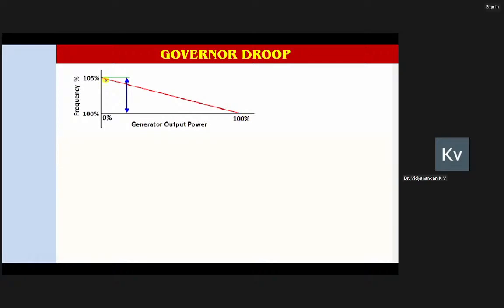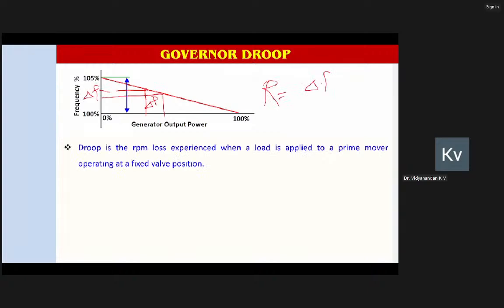Mathematically, droop is defined as the ratio of change in speed for a change in megawatt. So if there is a change in frequency and there is a change in megawatt, droop capital R is defined as delta F divided by delta P. That is, for an incremental change in speed or frequency, how much is the corresponding incremental change in the power output of the machine. This is the mathematical definition of droop.